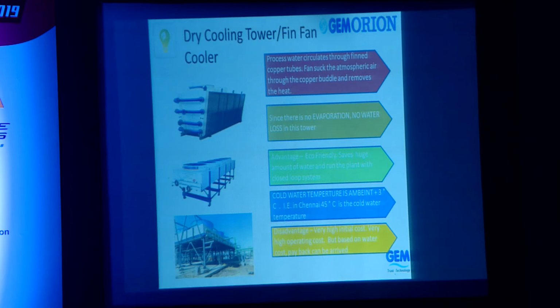Another method by which we can conserve water is to go for a dry cooler, or a typical fin fan cooler. These fin fan coolers are nothing but extended fin radiators, tubes with fins. Water circulates inside the tubes and has no direct contact with the air outside. Air exchanges heat through the fins and removes the heat from the process. It can be designed in various configurations. The temperature we can get from this type of system, if you use a dry cooler, will be ambient plus maybe 2 or 3 degrees only. There are some process requirements, like oil temperature, that can be maintained using this kind of system.